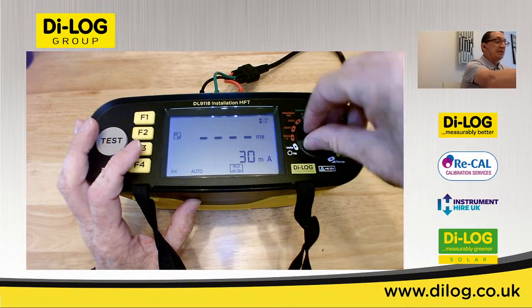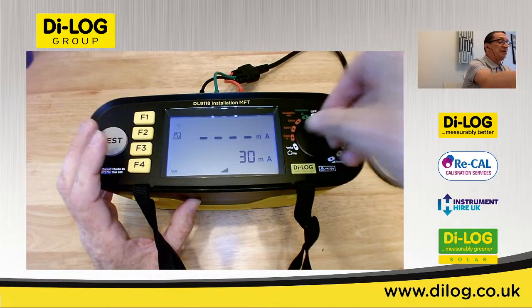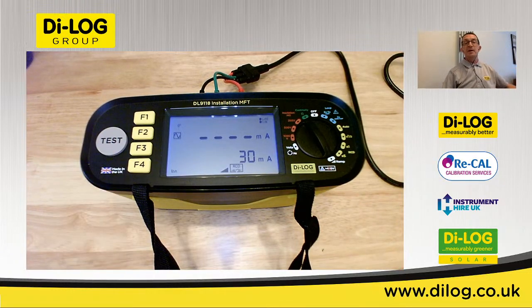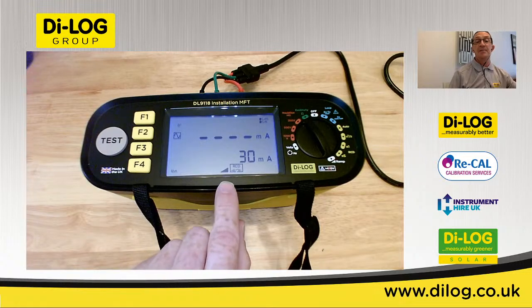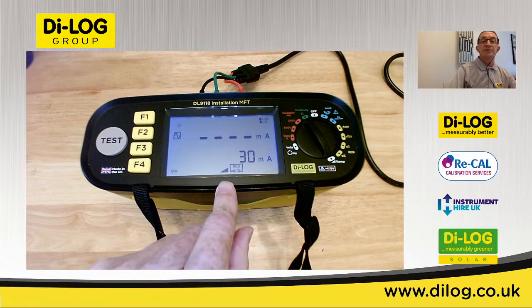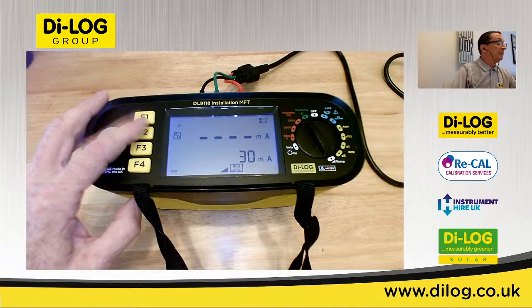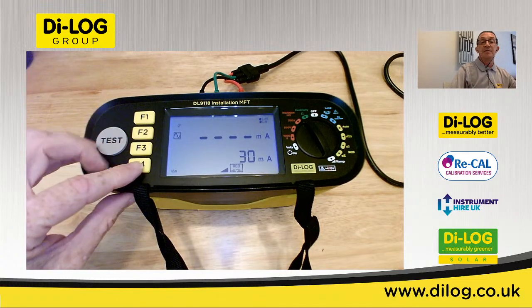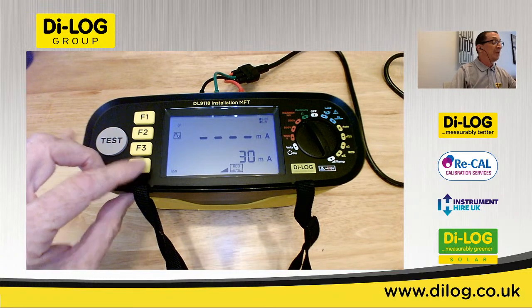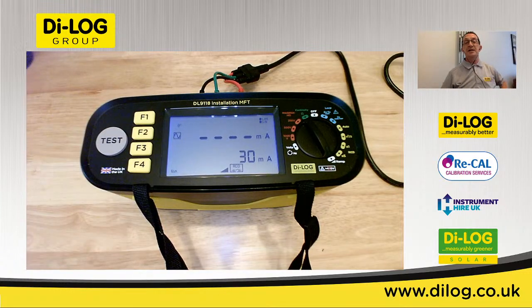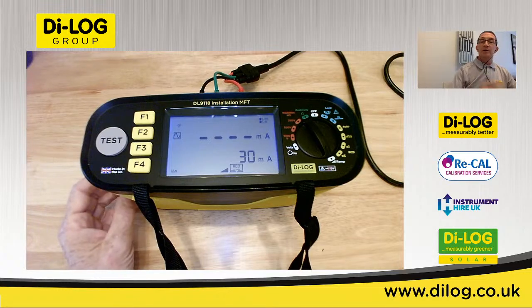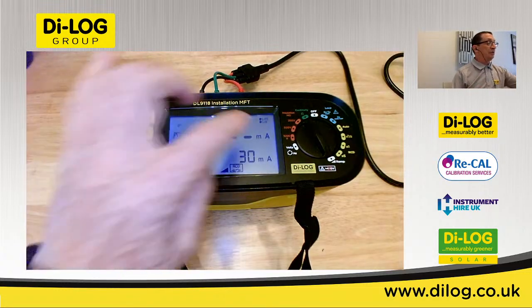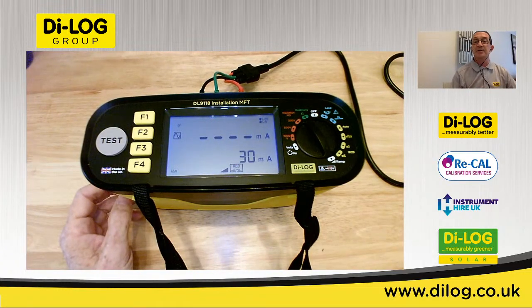Another very useful test while we're talking about RCDs, particularly if you've got nuisance tripping, is a ramp test facility indicated by the ramp symbol at the bottom of the display there. So again, type of RCD we're testing, function 4 changes the rating, and if we press the test button on the RCD, I won't do it because it might knock my house out, but the RCD will trip out and it'll give you actual tripping current in milliamps displayed on the tester screen.